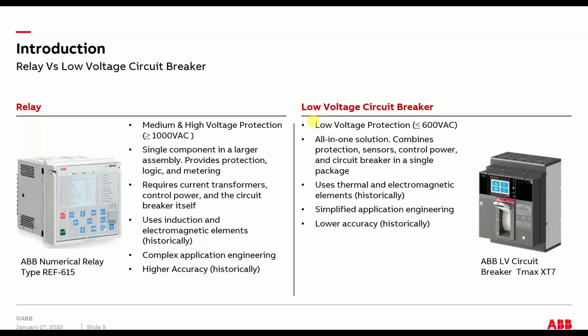Whereas a relay provides only the smarts for the system. It's only the protective functions and maybe some logic for control, maybe metering, but it's not the circuit breaker, and it's not even the sensors. The circuit breaker, the sensor and the breaker mechanism in a low voltage breaker all come together as one big package. So the relay requires sensors, which are typically current transformers, and control power. That's another important thing: they're not self-powered. You need some sort of reliable power source, battery or UPS, in order to have the protection system work at all. And then the circuit breaker itself.